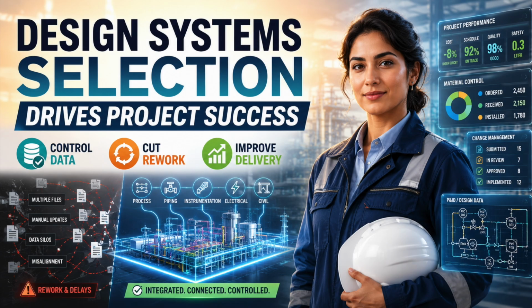Commissioning must be considered early. Systems and subsystems should be defined while engineering data is still being developed. Equipment, lines, instruments, cables, and documents should be allocable to commissioning boundaries. When this structure is delayed, commissioning teams are forced to reconstruct thousands of relationships manually under schedule pressure.